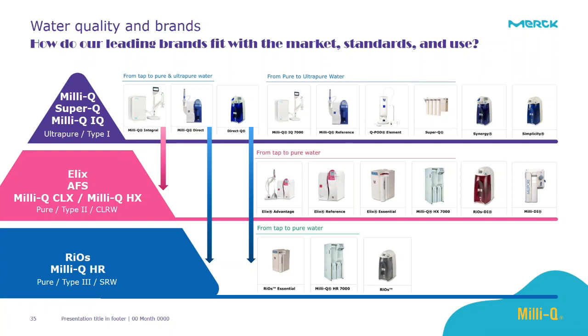Second group of instruments, we have the type 2 water purification systems: Elix Advantage, Elix Reference, Elix Essential, Rios DI, MilliDI, and the recently launched Milli-Q HX 7000. This machine can produce up to 150 liters per hour of deionized water, and it can be connected in series. We can connect 3 machines in series to produce up to 450 liters per hour of deionized water. We have a very wide variety of products which can produce deionized water according to the daily consumption you need.